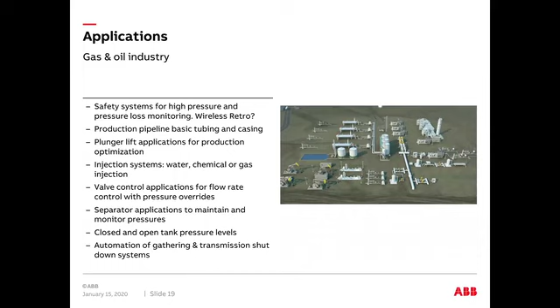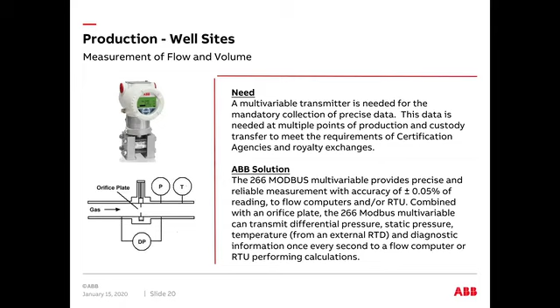One application is a multivariable transmitter, used to collect precise data when dealing with expensive chemicals or hydrocarbons, for royalty exchange. A good example: we have high-accuracy measurements going into an RTU giving you that information. A multivariable in a hydrocarbon pipeline application uses what's called an orifice plate to measure the pressure on each side of the plate, which gives you the differential, as well as the temperature.